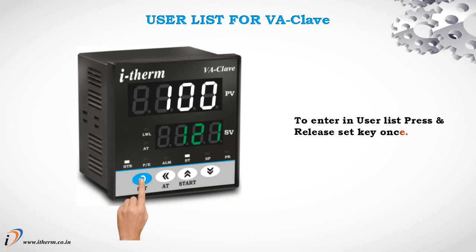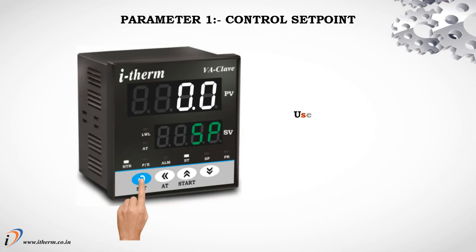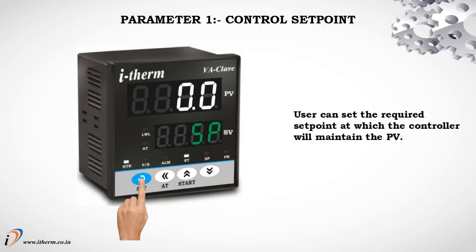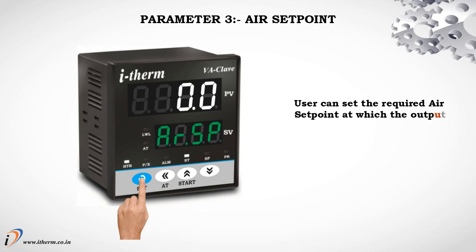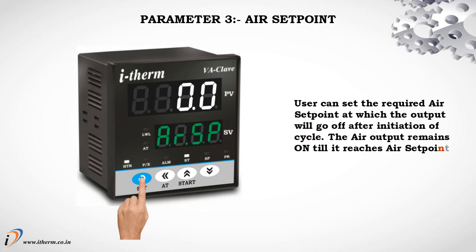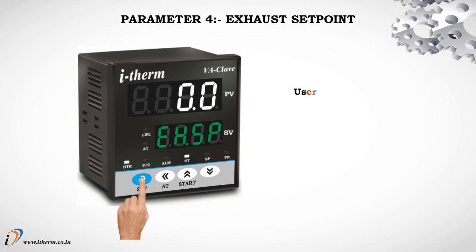User List for VA-Clave. To enter the user list, press and release the Set key once. Parameter 1: Control Setpoint. The user can set the required setpoint at which the controller will maintain the process value. Parameter 2: Soak Time. The time base for the soak timer is in minutes. Once the process value reaches the set value, the soak timer starts decrementing. Parameter 3: Air Setpoint. The user can set the required air setpoint at which the output will go off after initiation of the cycle. The air output remains on until it reaches the air setpoint.